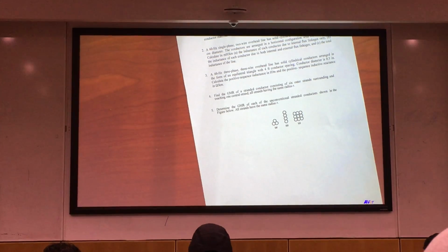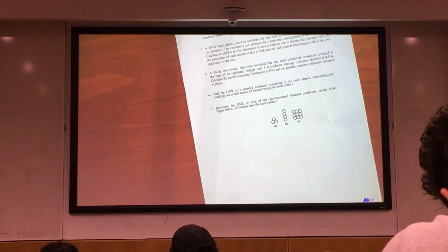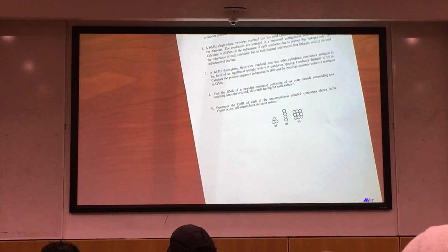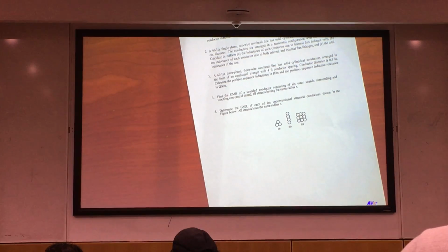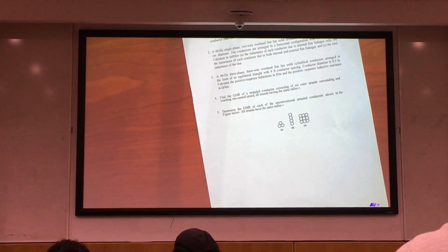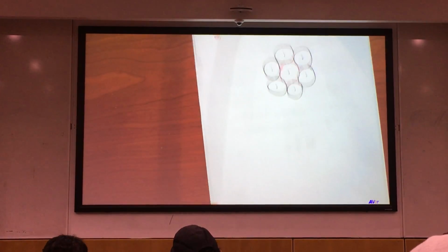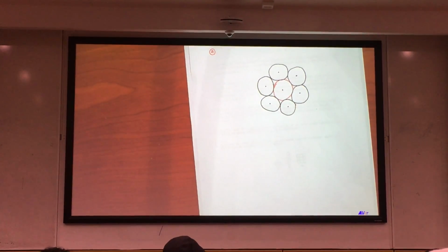Number four is just to train you on getting the geometrical mean radius for bundled conductors. So in this one we have 7 conductors: one internal conductor surrounded by 6 outer conductors representing one wire. And we need to calculate the geometrical mean radius for this one. So the internal one is the red one. All of them have equal radius, equal to r.